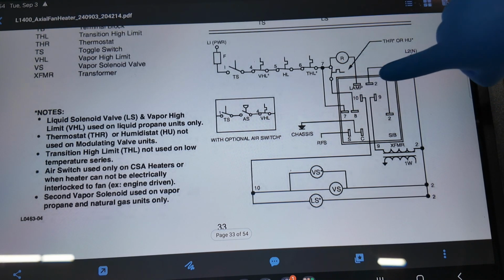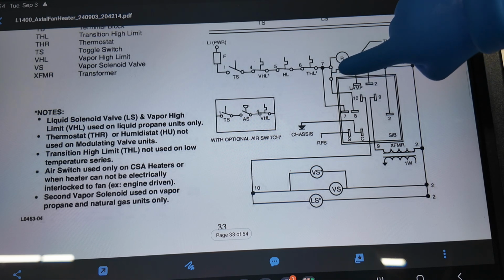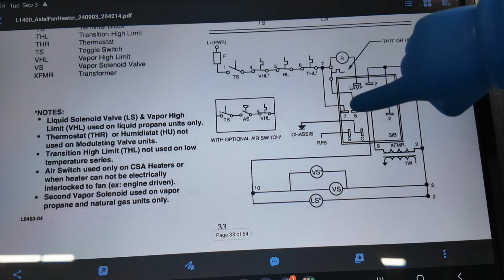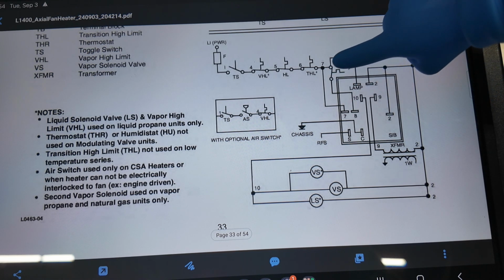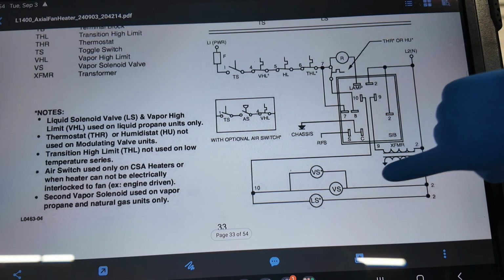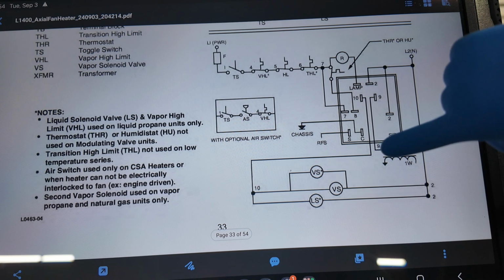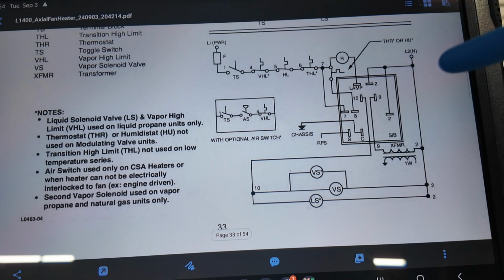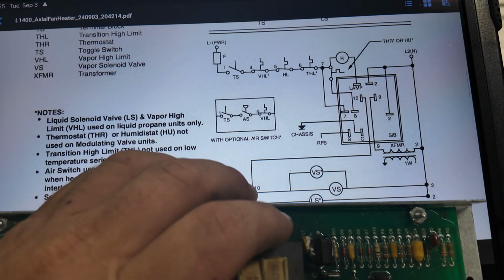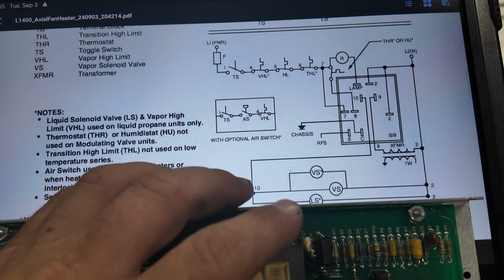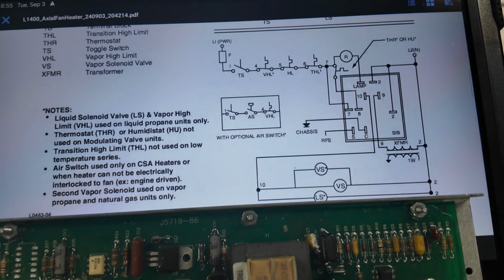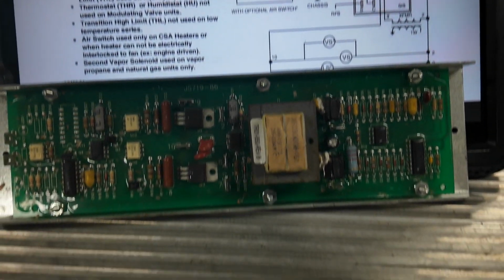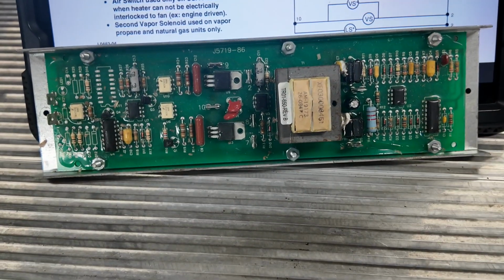Now, if you're running the burner with a mod valve, you will not have a thermostat. You will just have a jumper wire from 8 to 7 if you're running with a mod valve. Okay, with that said, let's look at the actual boards. That can be somewhat complicated. Let's look at the actual boards and see what we're actually working at. We're going to start off with the old style burner board.